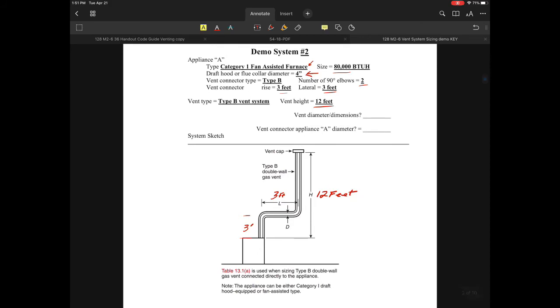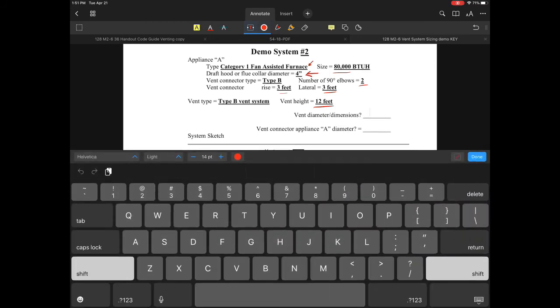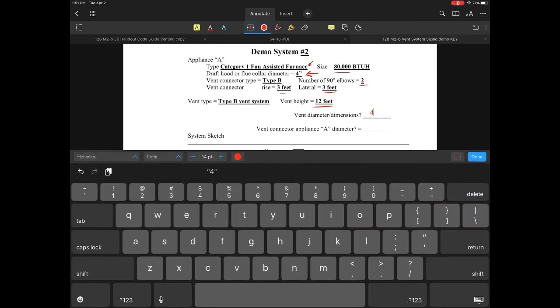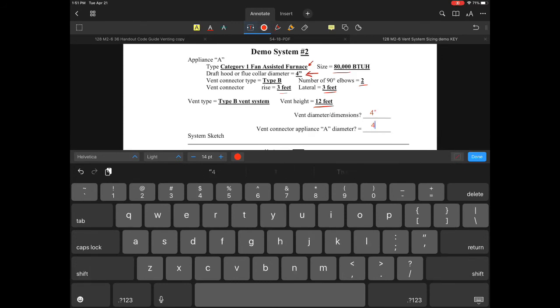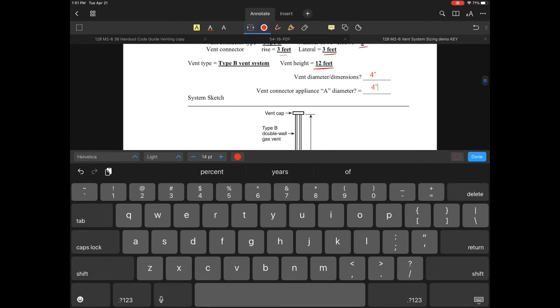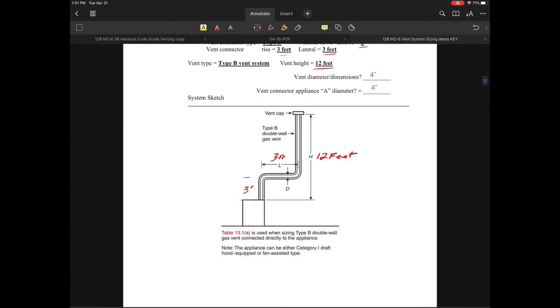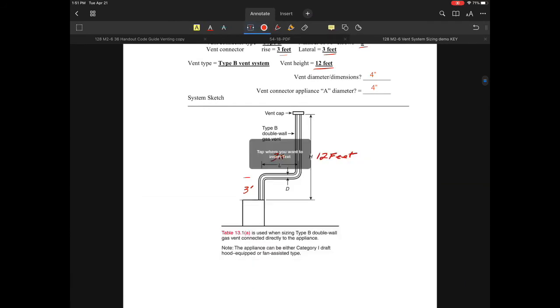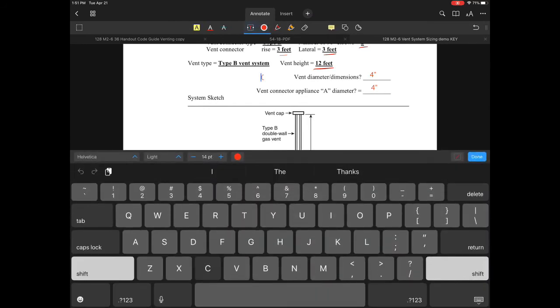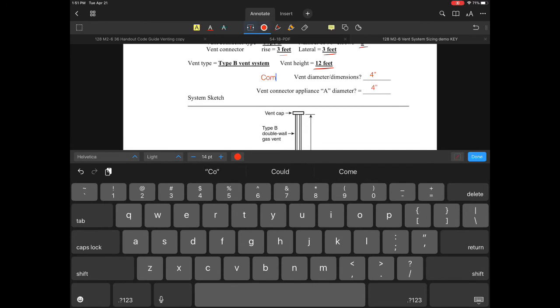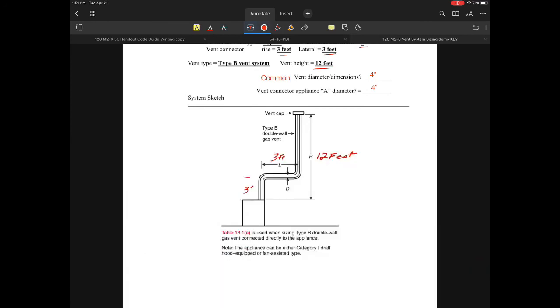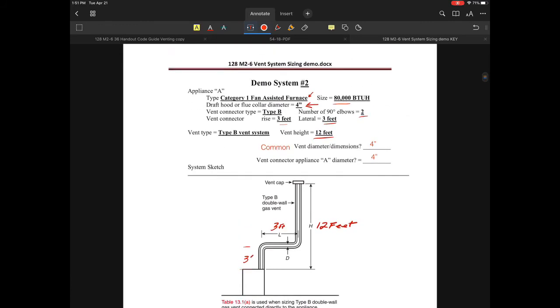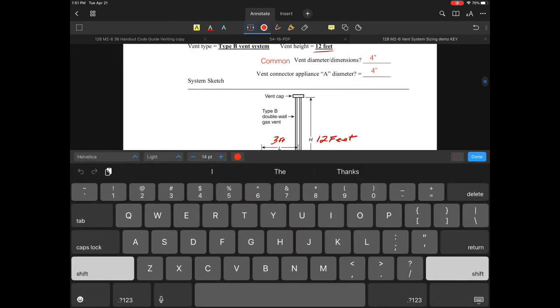Looking at our application, the common vent is a four-inch vent system. The connector is also four inches. The vent diameter and dimensions are all set. As for derating, our vent height is good with no problems. We don't have too many elbows—if there were more I'd have to derate the tables. No derating required.